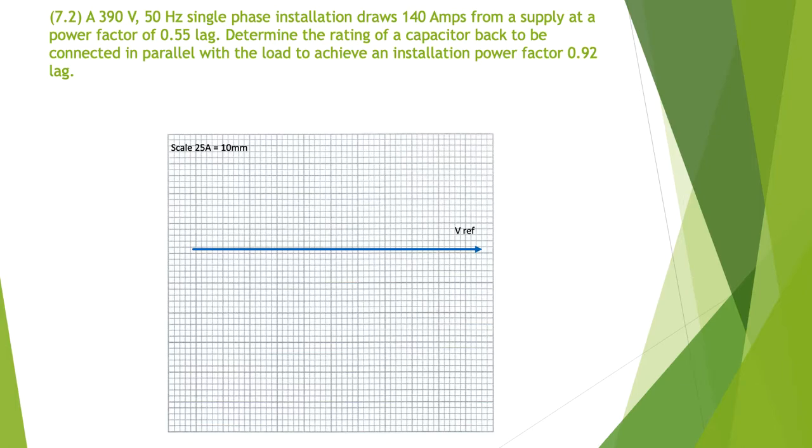Problem 7.2: A 390 volt, 50 hertz single phase installation draws 140 amps from a supply at a power factor of 0.55 lag. Determine the rating of a capacitor bank to be connected in parallel with the load to achieve an installation power factor of 0.92 lag. These are the two critical pieces of information we need.